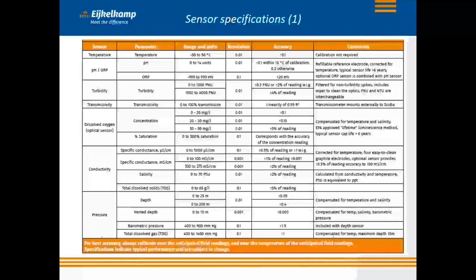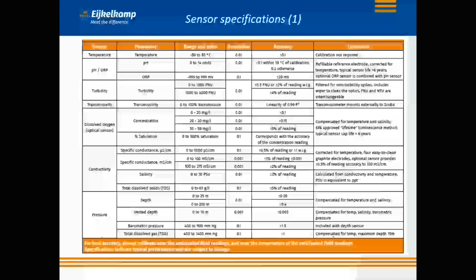For all sensors, there's a remark: for best accuracy, always calibrate near the anticipated field readings and near the temperature of the anticipated field readings. Specifications indicate typical performance and are subject to change.